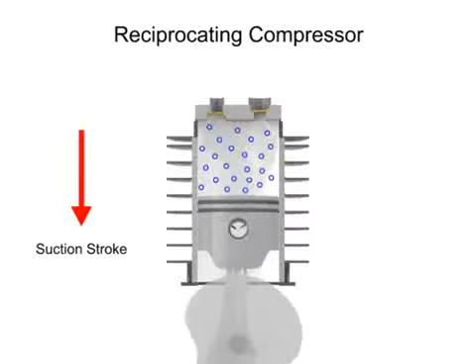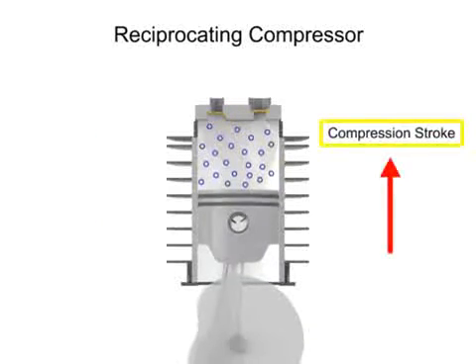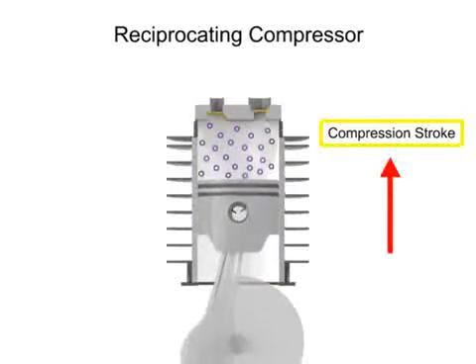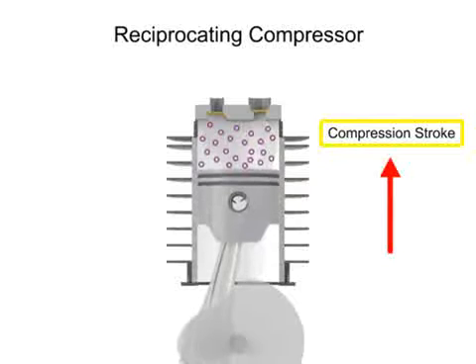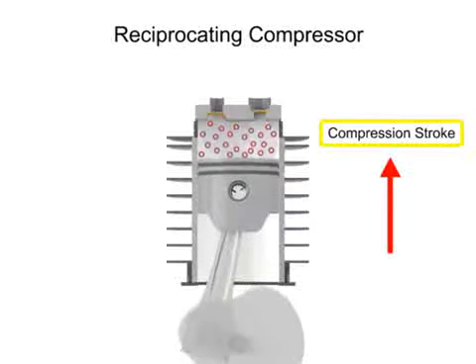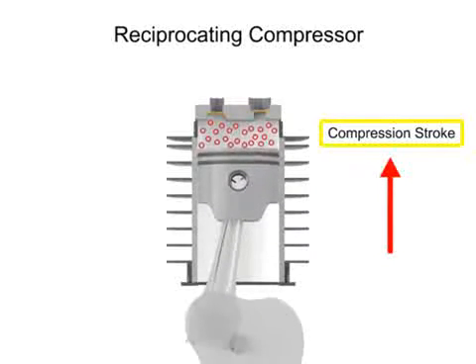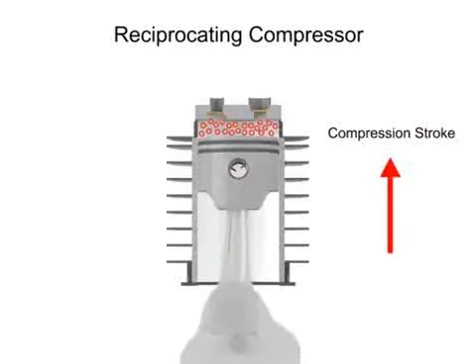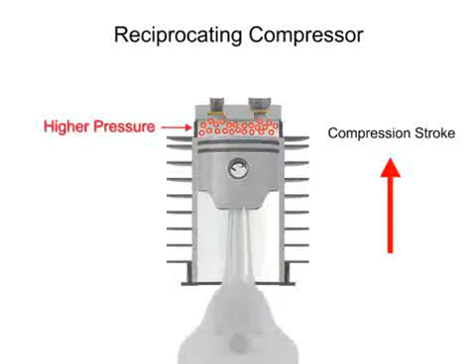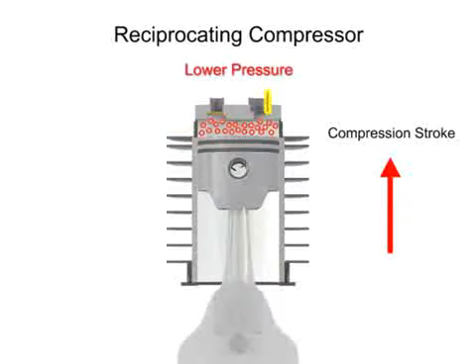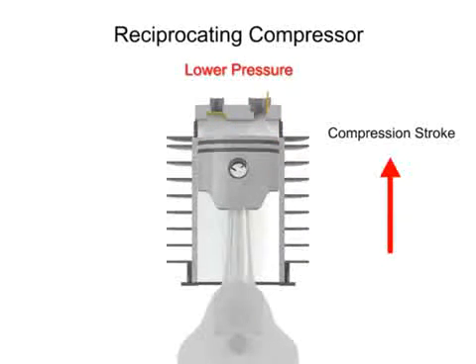The upward stroke is called the compression stroke. As the piston begins its upward compression stroke, the volume within the cylinder decreases. The decrease in volume causes the pressure within the cylinder to increase, which opens the outlet valve and compressed air discharges from the cylinder.